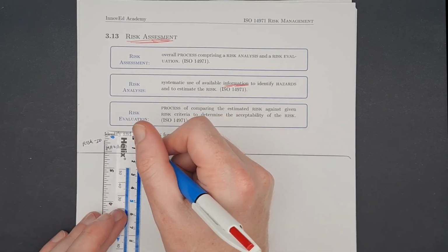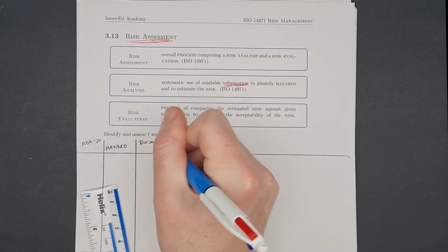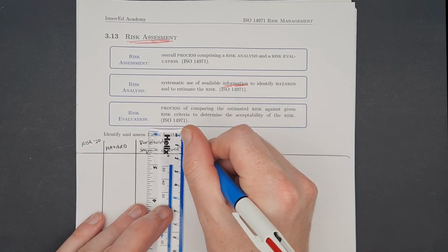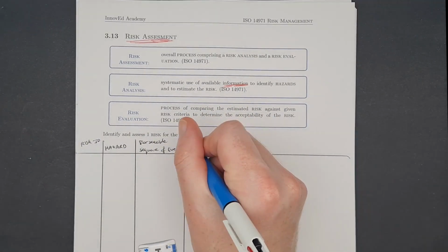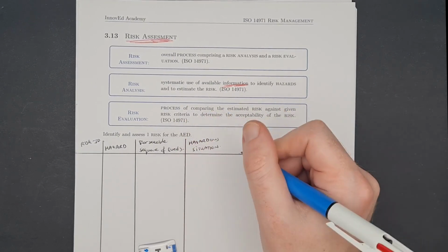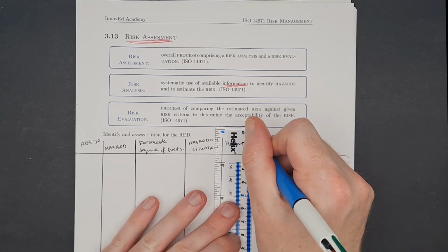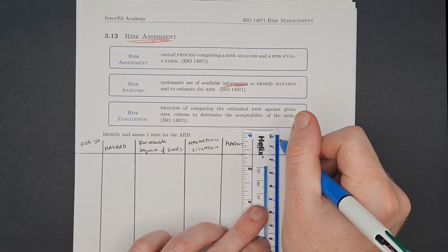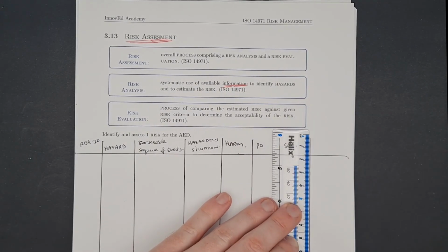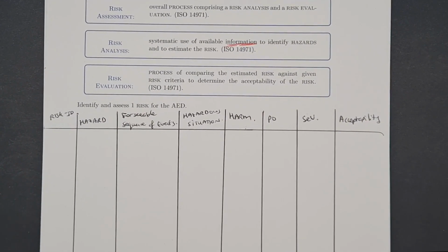You can see in the headers there, I have risk ID, which is going to be what we use for our design traceability. Then we identify our hazards, which is the first part of this. Then we ask what is the foreseeable sequence of events that will lead to a hazardous situation that could cause harm to either people or property. And then we look at what is the probability of that harm actually occurring, and if that harm were to occur, what is its severity? Then based on these two, we'll ask, is this risk acceptable or not acceptable?